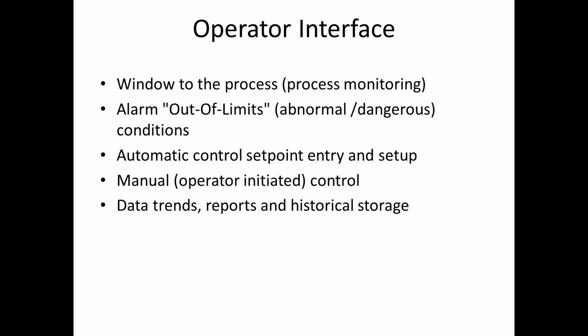And like I said, the operator interface system was the window to the process that lets you actually monitor the process. The operator interface system would be able to tell you if there are some processes that were getting out of limits, whether it was abnormal or a dangerous condition. Maybe, for example, your DO levels were reading 5 parts of oxygen in the aeration basin, and your normal set point for the DO in the aeration basin was maybe 1.5 to 2, maybe even 2.5, but you knew that 5 was really kind of abnormal. So that let a person go out there and troubleshoot, maybe find a valve that was sticking or something like that.